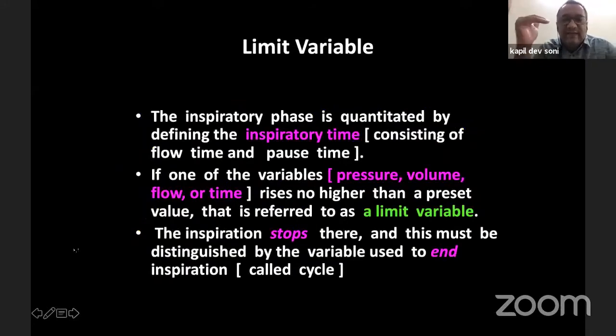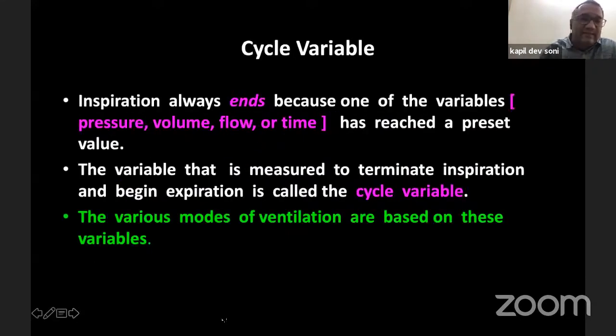The limit variable can be what you have set on the machine. If you are working in a volume control mode, then after a preset amount of volume, the machine would stop giving further volume. So it can be volume controlled, it can be pressure controlled, just like a set pressure is achieved and then the machine does not give further breath. So that can be a limit variable. Sometimes in certain modes, it can be a time variable as well. So what does it mean? The inspiration stops there, and this must be distinguished by the variable used to end inspiration, which we call the cycling variable. A cycle variable, again, can be pressure, volume, flow, and time. These are the only 4 variables in the ventilator. A variable that is measured to terminate inspiration and begin expiration is called the cycle variable. And this could be time cycled, volume cycled, or pressure cycled.